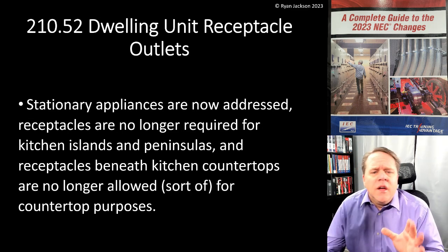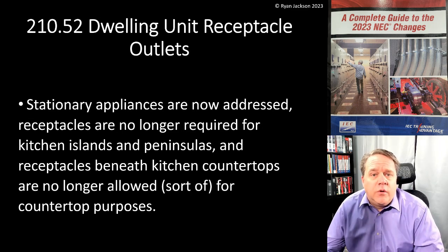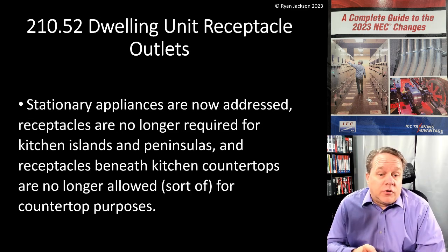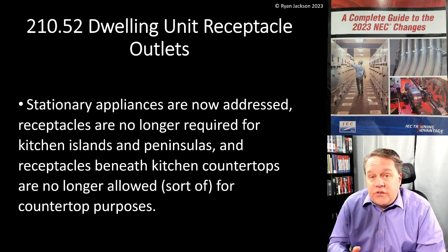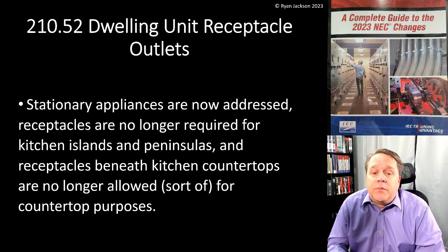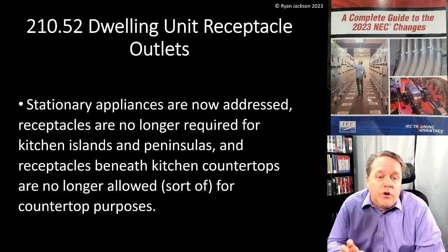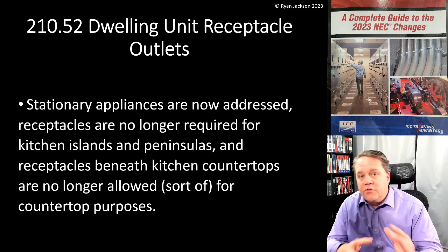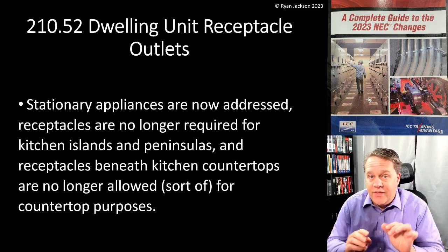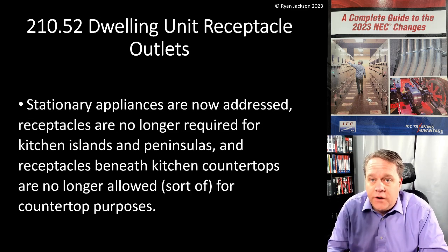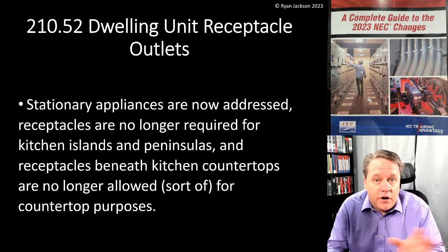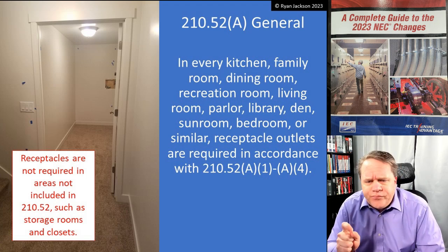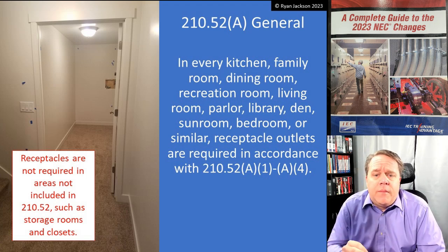Here are the key changes: stationary appliances are now addressed in 210.52, receptacles are no longer required for kitchen islands and peninsulas, and receptacles beneath kitchen countertops are no longer allowed for countertop purposes — though that one is nuanced. Let's get into 210.52A.